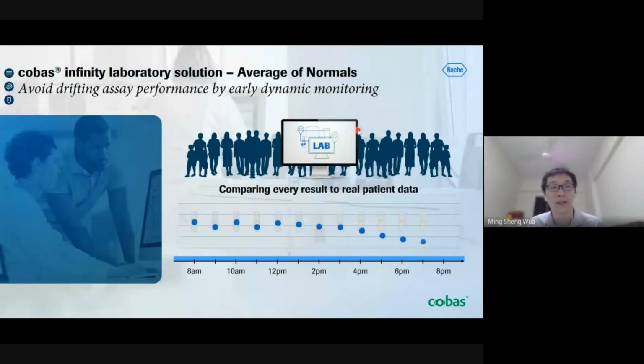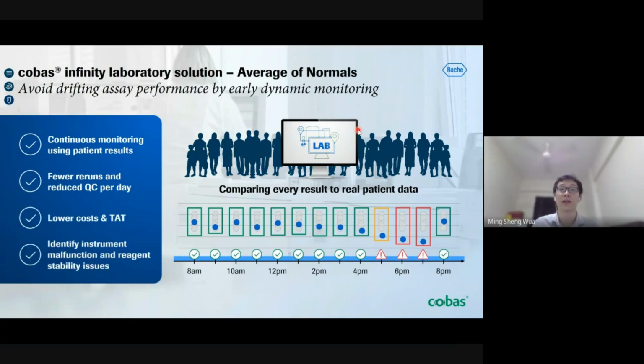Also part of the Cobas Infinity solution is the average of normal, or sometimes we call it patient-based real-time quality control. Essentially, this is to monitor the performance of your analyzer by using the average of your patient results. How will this be helpful? Conventionally, most labs will run QC either twice per day or once per day. Imagine you are a lab running QC only once per day in the morning, for example at 8 a.m. Every day you run your QC at 8 a.m., and throughout the rest of the day you don't run any QC.